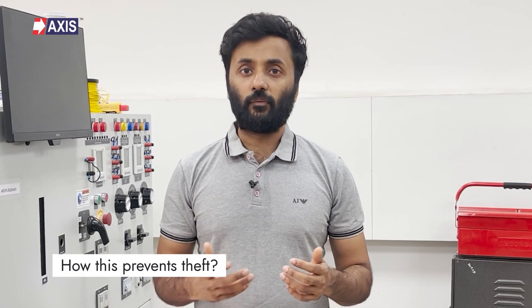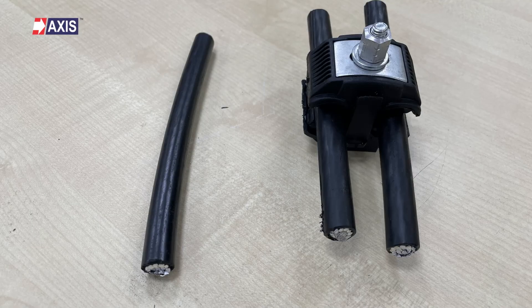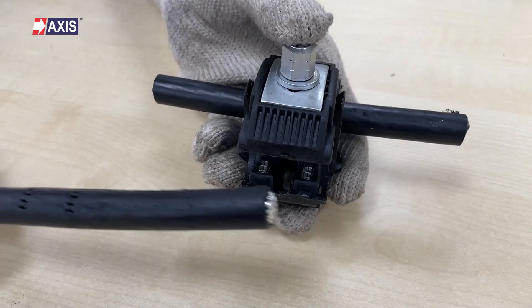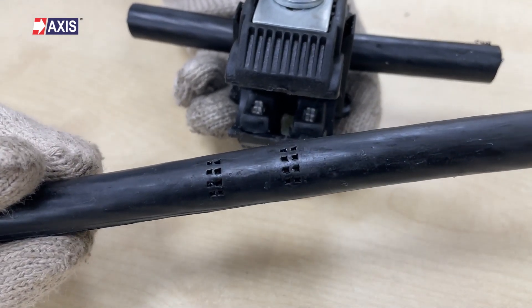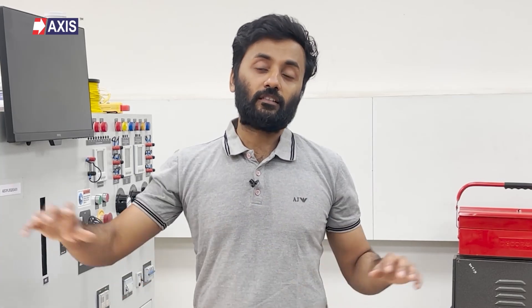Let's talk about how this prevents theft. Thieves steal electricity by stripping the cable's plastic cover and hooking wires to the metal lines inside. This is very easy to do with traditional bare conductors because there isn't any insulation to strip. AB cable systems and IPCs are different — the metal cable stays fully covered by its plastic jacket, and IPCs simply pierce through the jacket to reach the metal conductor inside without uncovering them. After piercing, the IPC covers and seals the hole.